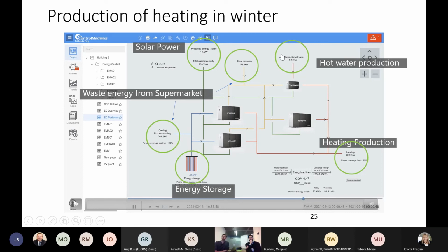Also, you see we're delivering domestic hot water for the different stores during the day. So this is how we typically operate in winter. During the night, we take a lot out of the energy storage, but during the day, in this case, we can take all the heat we need for the shopping center directly from the waste heat.